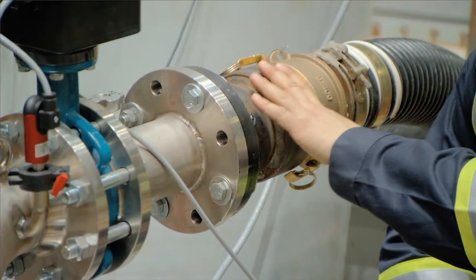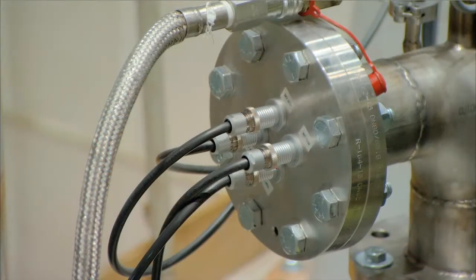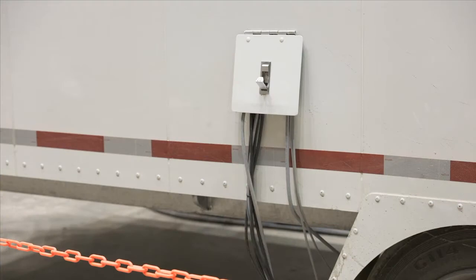Connect the flexible vacuum hoses to the vacuum flange. The oil circulation connection fittings have to be connected to the transformer, and the connection has to be free of leaks. Connect the temperature sensors for measuring the object temperatures, if applicable. Connect the signal cables to the oil treatment plant.